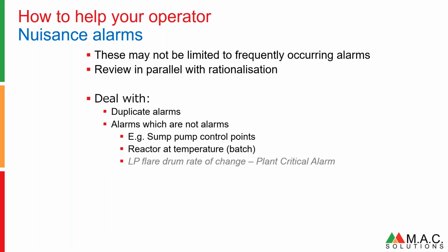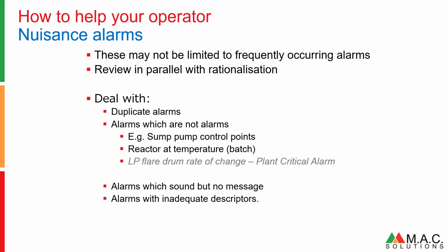The senior operator came charging out of his office while I was there. "What's that? What's that?" It had its own individual plant critical alarm sound. "Oh, it's just the LP flare drum reset again. Sort the calculation." The operators became numbed to the fact that plant critical alarms happened and we don't need to do anything. "I've told them about it. Nobody listens. Nobody ever does anything. Why should I bother? Why should I care?" We come back to that.